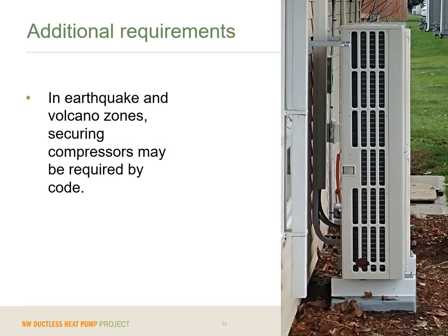If you are installing west of the Cascade Mountains or in an earthquake or volcano area, you may actually be required to put specific earthquake straps on. If you look at this picture, near the top, you'll see a strap from the top of the compressor being mounted to the wall. And there are lots of codes and jurisdictions starting to require this, so you may really want to consider this a standard part of your installation process if you are installing ductless heat pumps west of the Cascades.